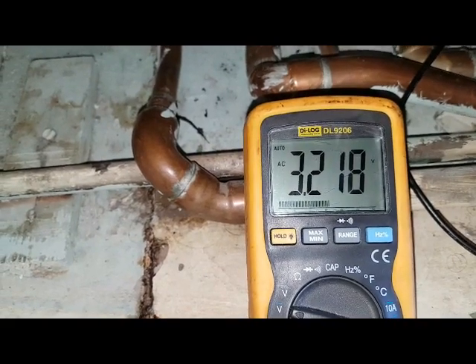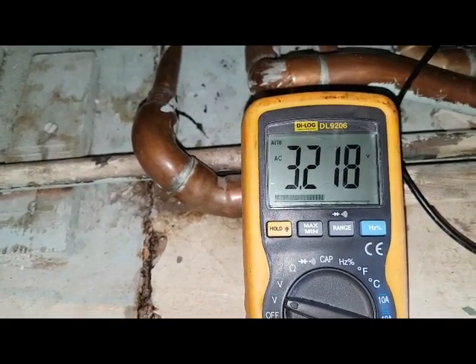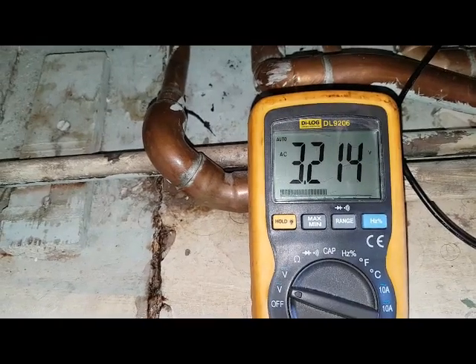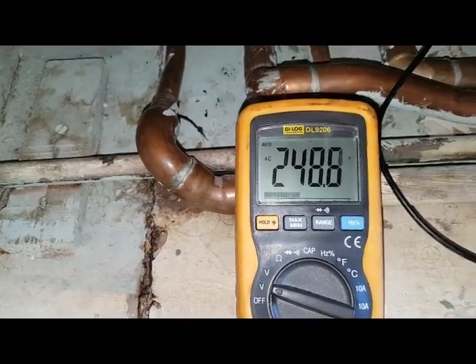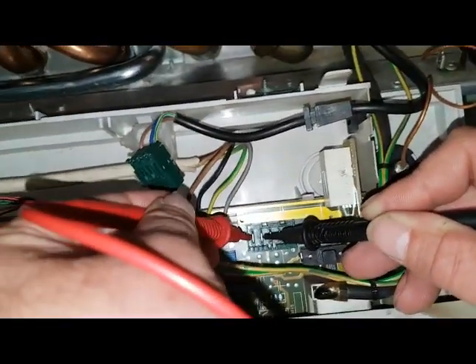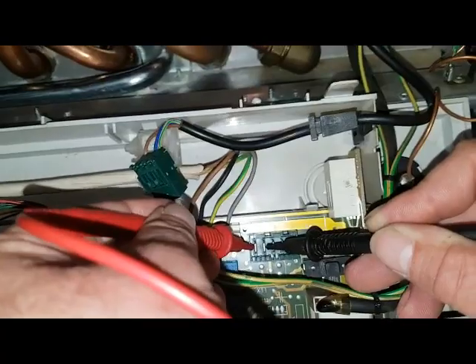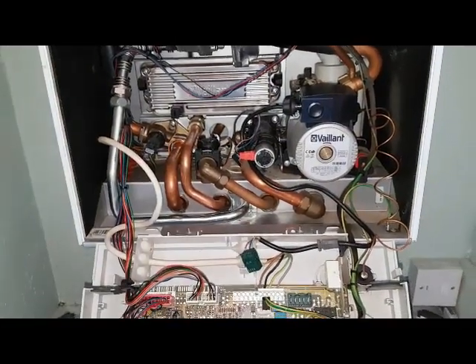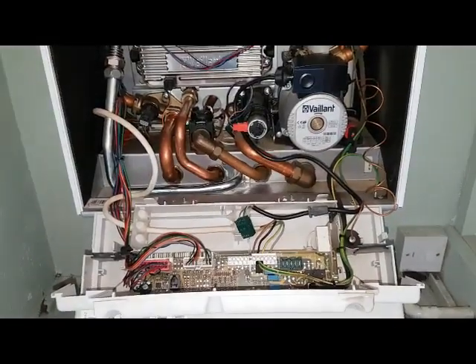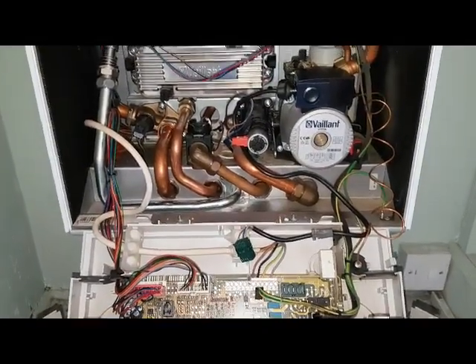You'll see it disappear now because what it does is pulse — it sends power out just for a short spell. And there you go again. As I said, that connection there verifies power going to the pump, so that was the end of this diagnostic to verify that it is the pump.